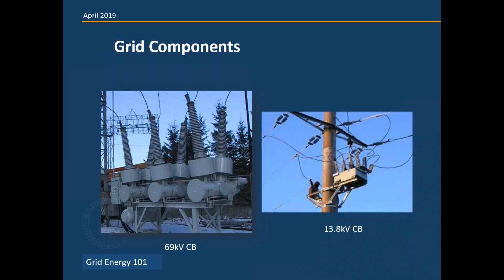Here's an example of a 69 kV circuit breaker. And then on our distribution system, on the right-hand side of the screen, is an example of a pole-top mounted 13.8 kV circuit breaker. A lot of the times on the distribution system, they'll put these out on different sections of the line. So as faults occur on the line, they'll just isolate a smaller section of the system. Next slide, please.